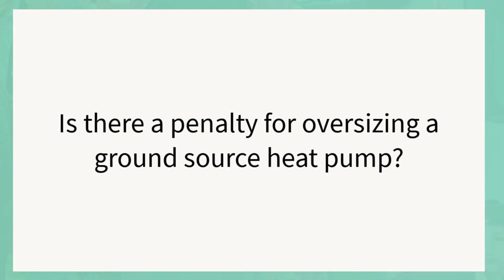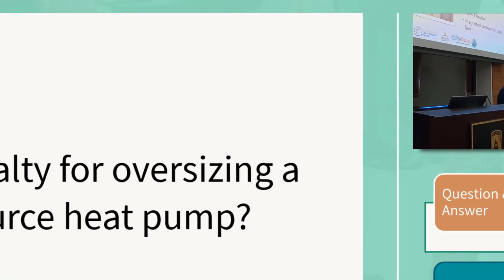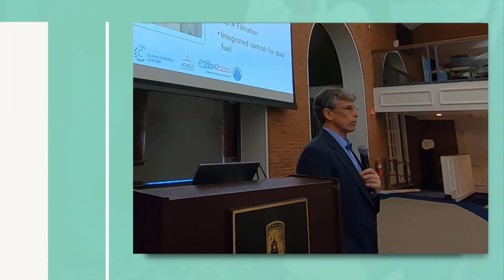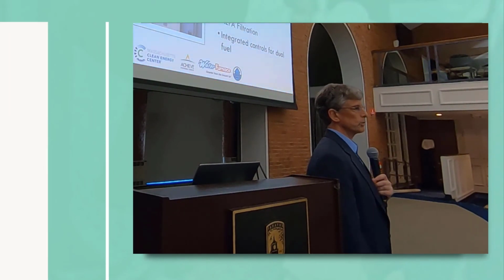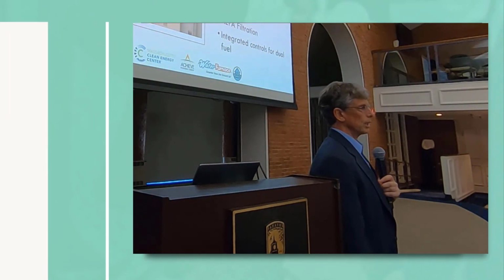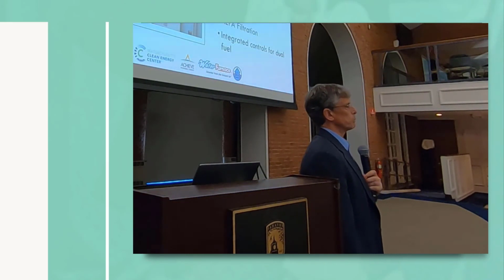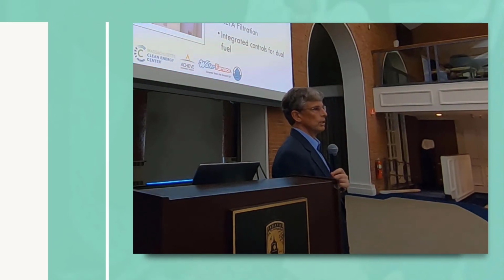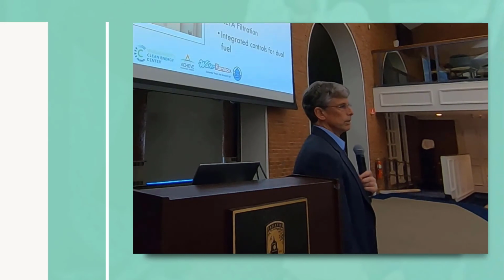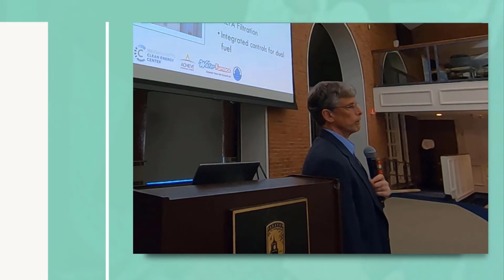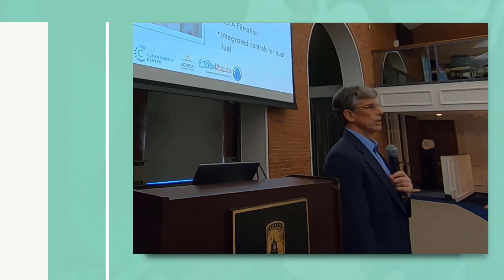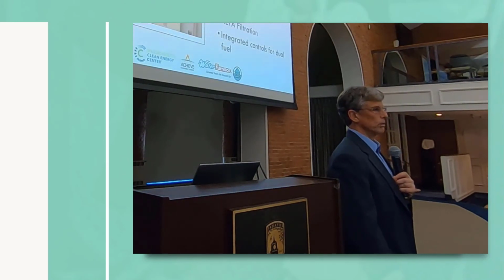And there are two. One is if it's oversized, you've done that much more drilling or whatever technology used to put in the ground heat exchanger, so you've spent money at the initial stage. And then secondly, you're spinning a larger compressor, so it takes more energy. It's better if it's variable speed. If it's variable speed, it helps a lot. But even then, those variable speed units can only modulate down to a certain point.